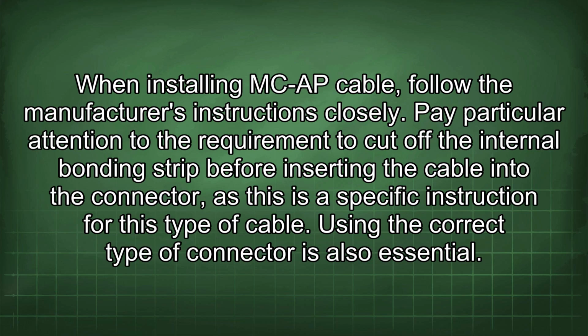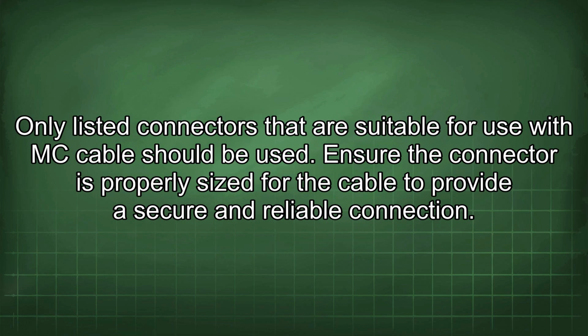When installing MCAP cable, follow the manufacturer's instructions closely. Pay particular attention to the requirement to cut off the internal bonding strip before inserting the cable into the connector, as this is a specific instruction for this type of cable. Using the correct type of connector is also essential. Only listed connectors that are suitable for use with MC cable should be used. Ensure the connector is properly sized for the cable to provide a secure and reliable connection.